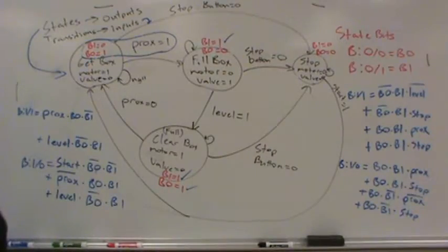So look at rung two and rung three. I'm going to cheat. You see what that does? So basically, rung zero and rung one will calculate what those state bits should be. Where are we going? And then these lines, lines two and line three, actually take us there. That way, this rung, rung one, has a chance to compute state bit one properly. So when state bit one new is correct, then it'll pass, it'll just ride it over into here. Does it every time. So that way we're dealing with the state bits as a set and not as two separate things. That takes care of that little bug we would have had.